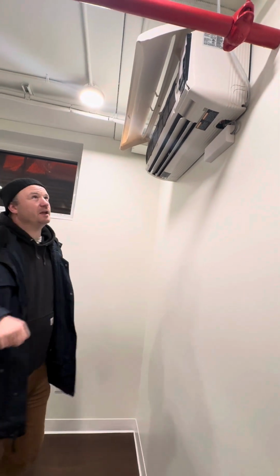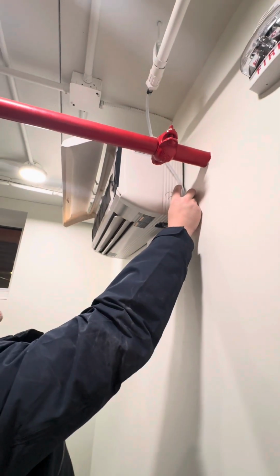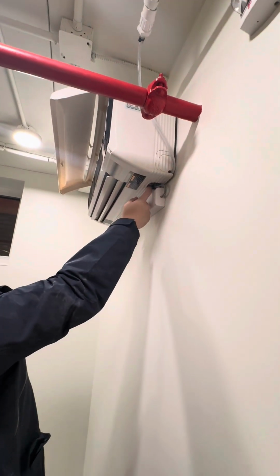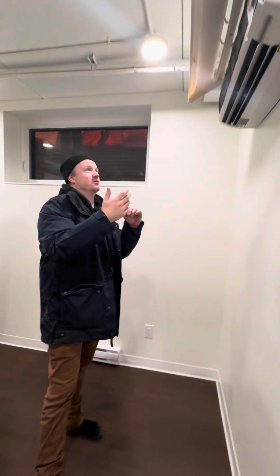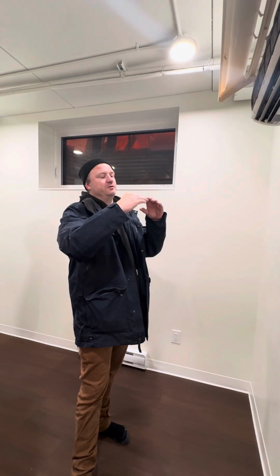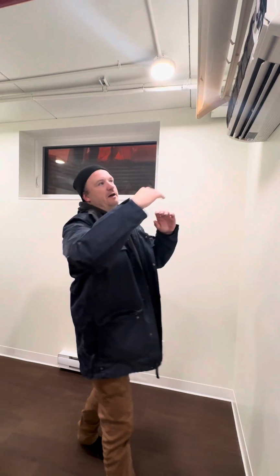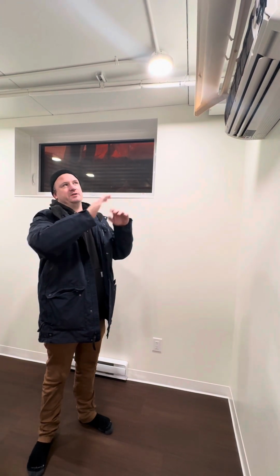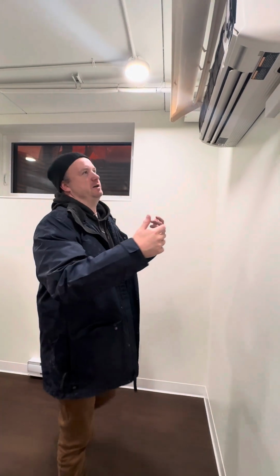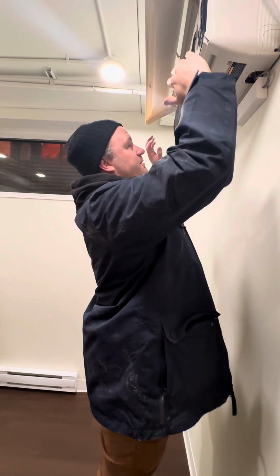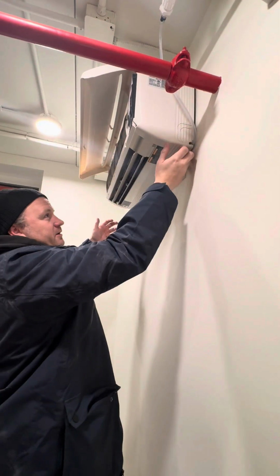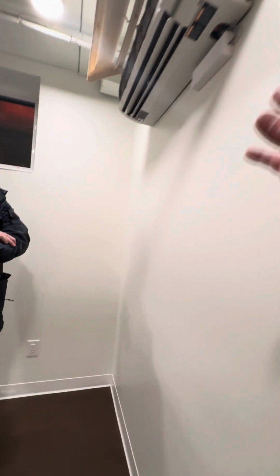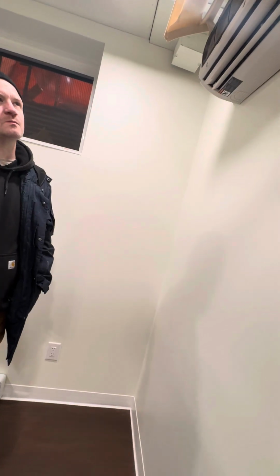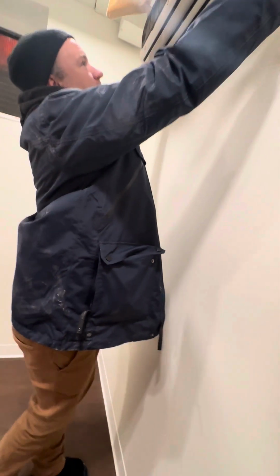Okay. There is a condensate pump. So the ones that you see that have tubing like this have an internal condensate pump that's installed behind here that has a float. So there's a particular alarm, I can't remember it off the top of my head, but it'll tell you a float alarm. So if you're overfilling that float, there's a little ring that comes up and it shuts it down, gives an alarm. These are on a bracket on the wall to get access to that thing. You may just have to pull the float out, clean it out, and get any gunk or anything. So we have to remove this cover here essentially.